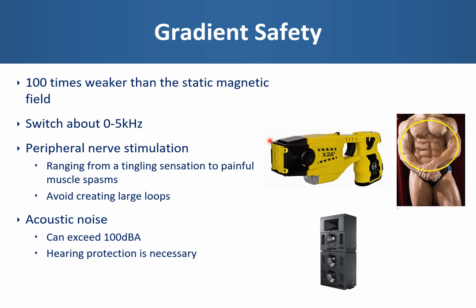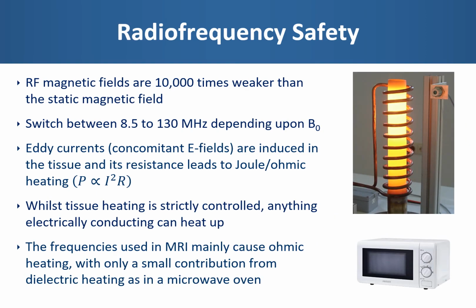In fact, the old MRI scanners used to have amplifiers which are typically used at rock concerts. So in certain pulse sequences, the acoustic noise levels can exceed 100 dBA. It's therefore necessary to ensure that anybody inside the MR environment or the magnet room during imaging has suitable hearing protection. The other major risk of serious injury in MRI is associated with the radio frequency field.